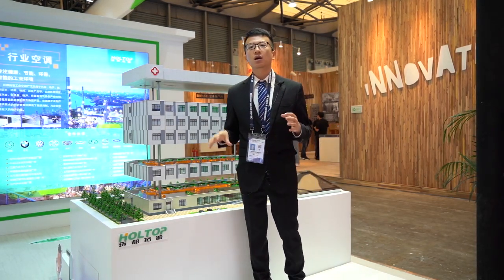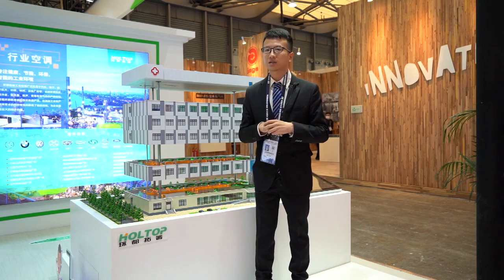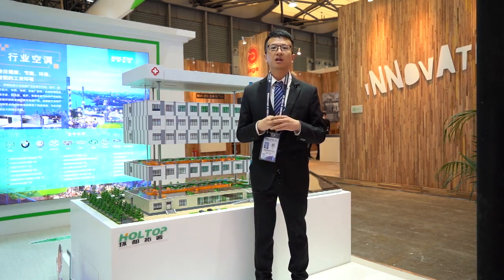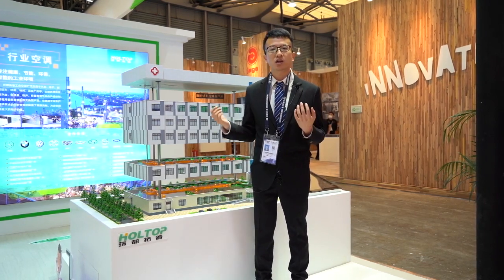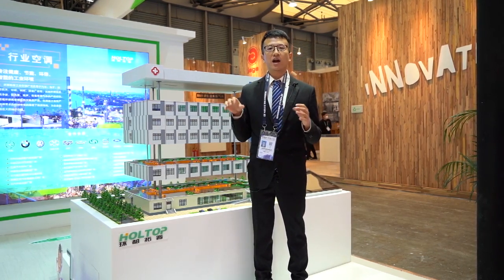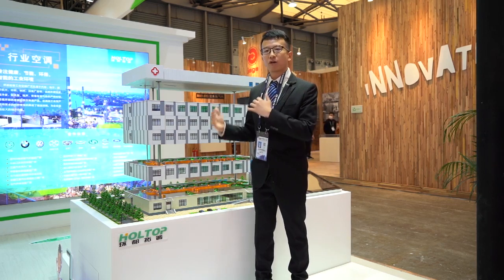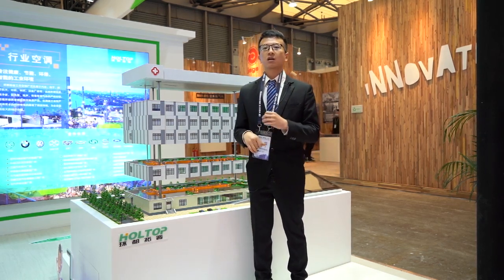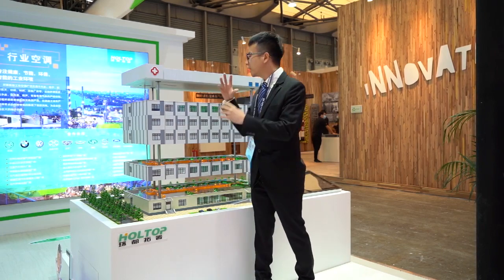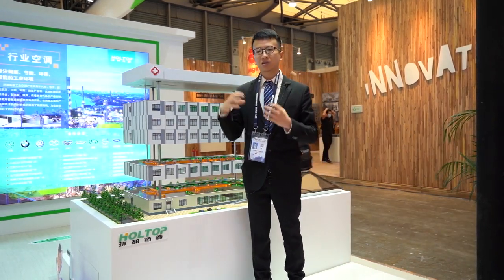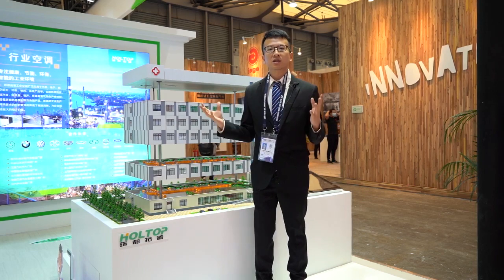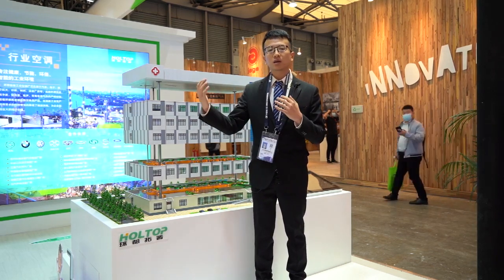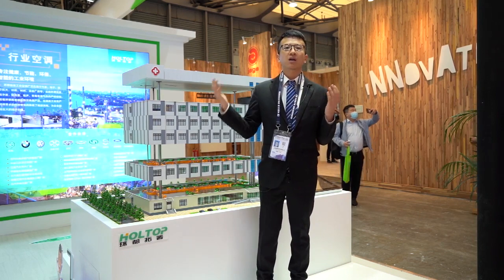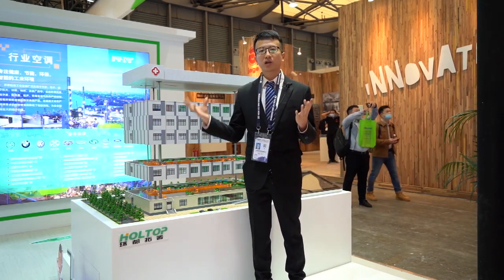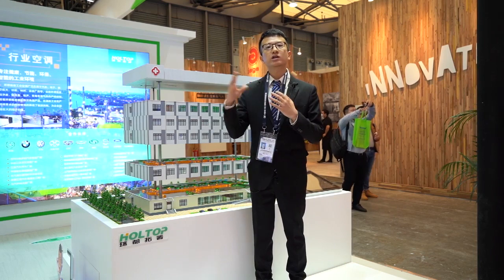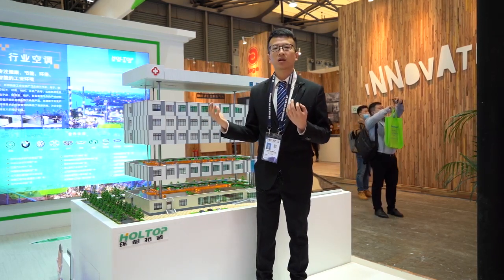And the fourth one is the energy recovery we just mentioned. In a hospital, 100% recirculation air is not safe and secure, because there could be air cross-flow contamination. For this reason, we have designed the energy recovery inside the smart fresh air system to exchange energy between the exhausting air and the fresh air, which means when the fresh air is inhaled from outside, maybe at 35 centigrade, it can mix with the circulation air at 25 centigrade.